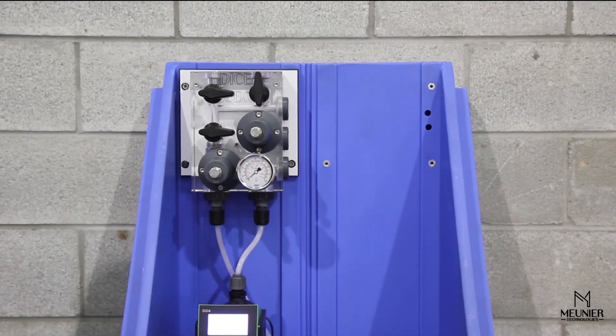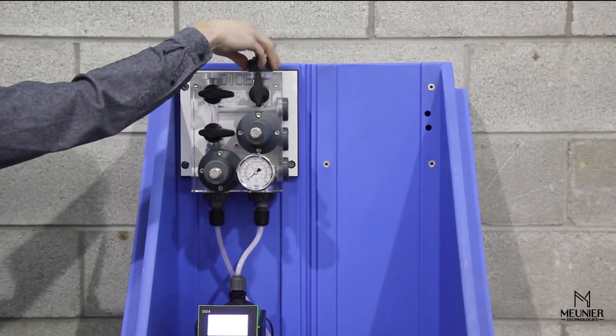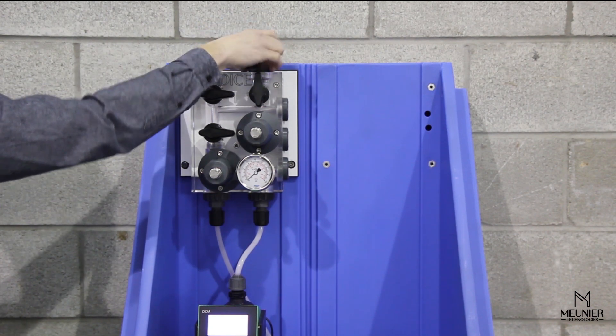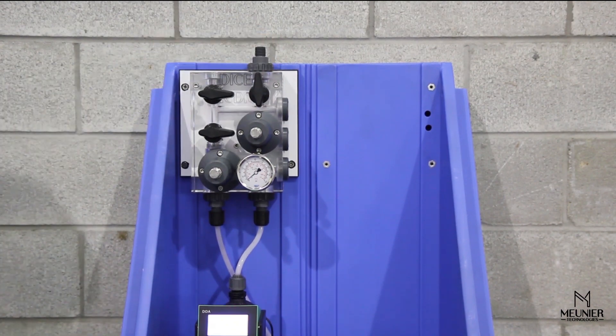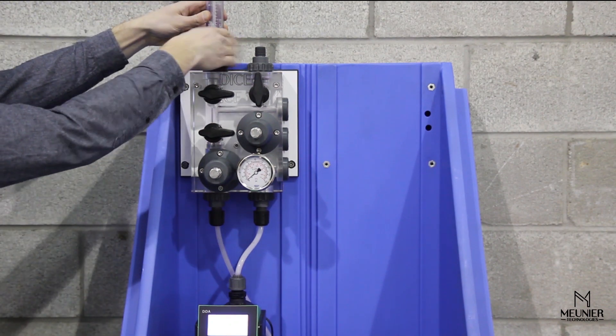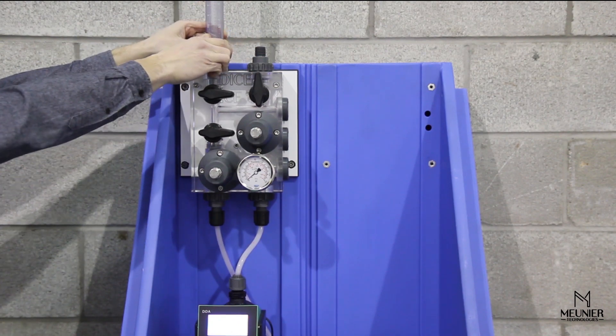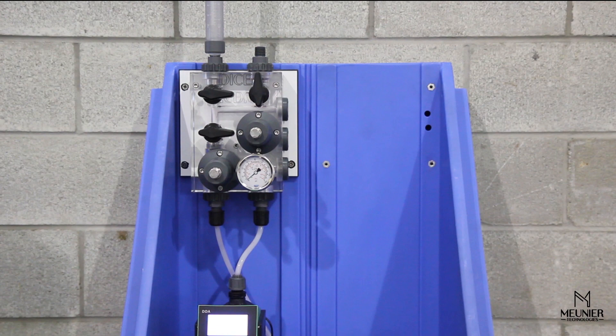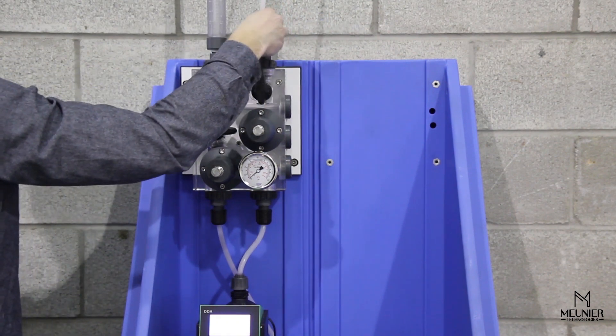Install the supplied DICE connectors on the process outlet port. Then install the calibration cylinder using the supplied DICE connector. In our case, we pre-assembled the bottom of the calibration column on the supplied DICE male MPT connector. Connect the process outlet line using the supplied ferrule connector.